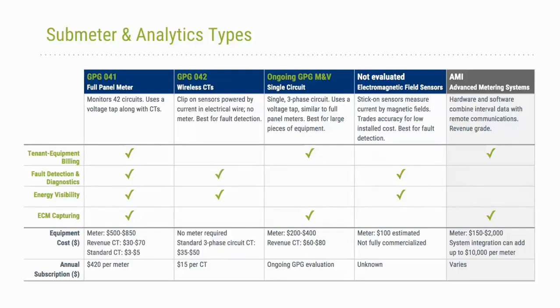As you can see here, we put the wireless CTs under the category of fault detection, diagnostics, and energy visibility. As I mentioned before, they successfully provided that type of service — they were able to identify 7 ECMs for a building. We didn't put them under tenant billing because of the high error rates observed during deployment.